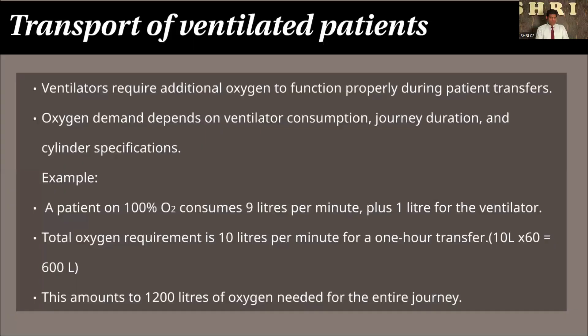Why do we always take the backup or buffer amount I mentioned previously? Because of unpredictable patient demand and system losses due to leaks in the pipeline. There can be faults in the regulators, and there can be increased wastage. So always check the devices completely before you travel to guard against leaks and device failures, but take ample oxygen.